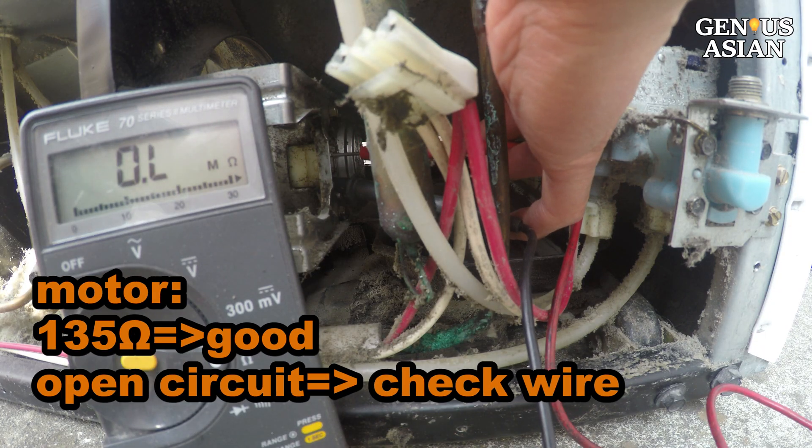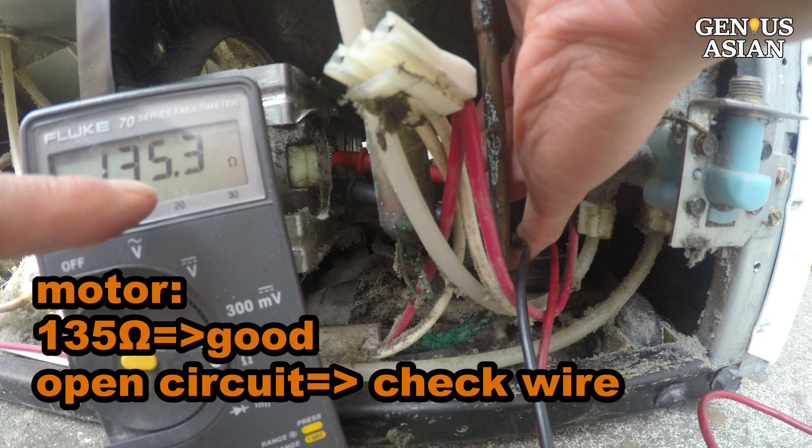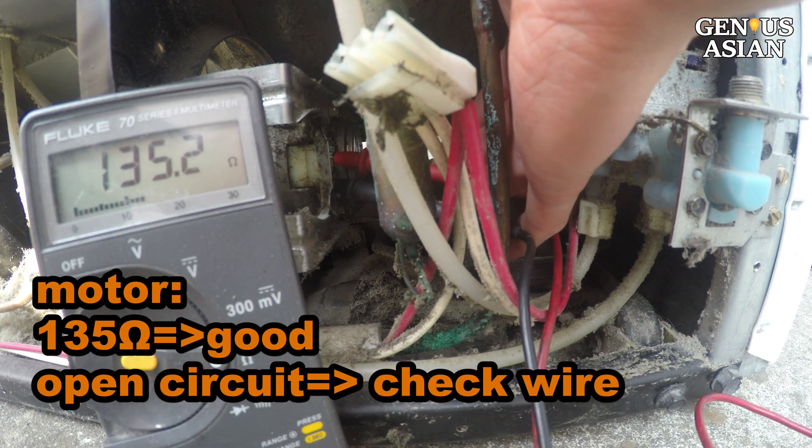Cover and seal the back panel space to have proper convection to cool the condenser coils. When you connect the meter probes to the motor and measure the resistance, if it is an open circuit — not 135 ohms — then you should check the connection or wiring. There is a disconnection somewhere.